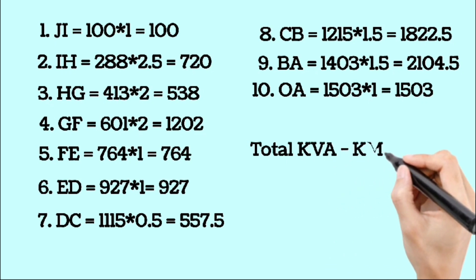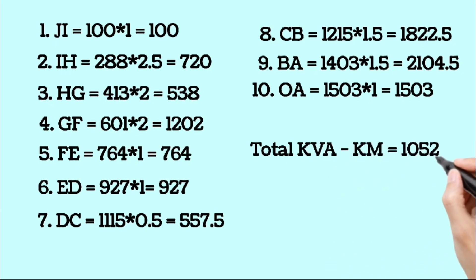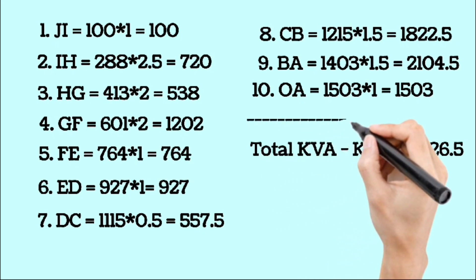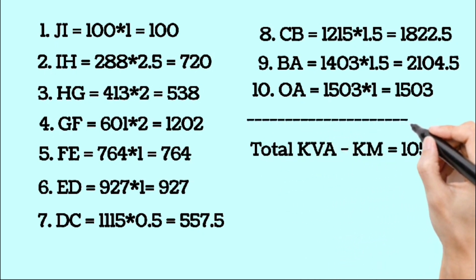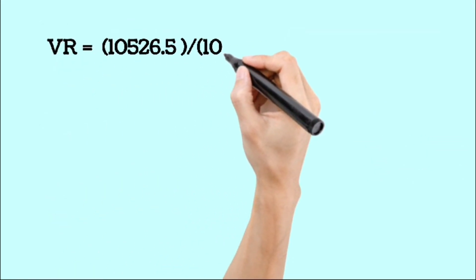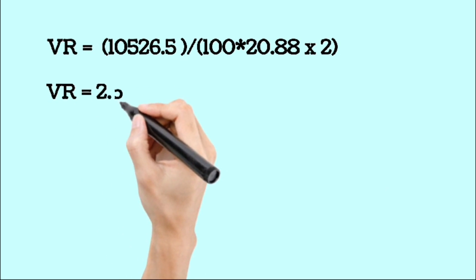Now substituting these values into the voltage regulation formula as we discussed earlier, finally the calculated voltage regulation is 2.52 percent. In this video we learned how to calculate voltage regulation in an 11 KV line at the tail end.